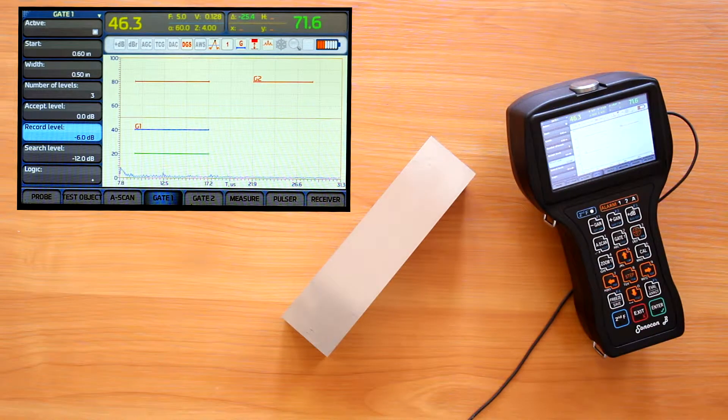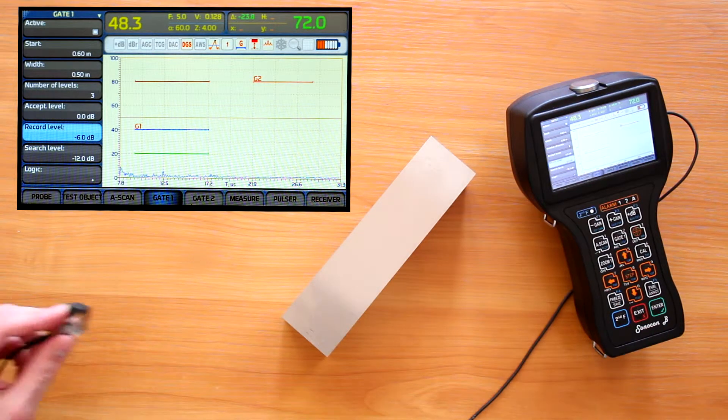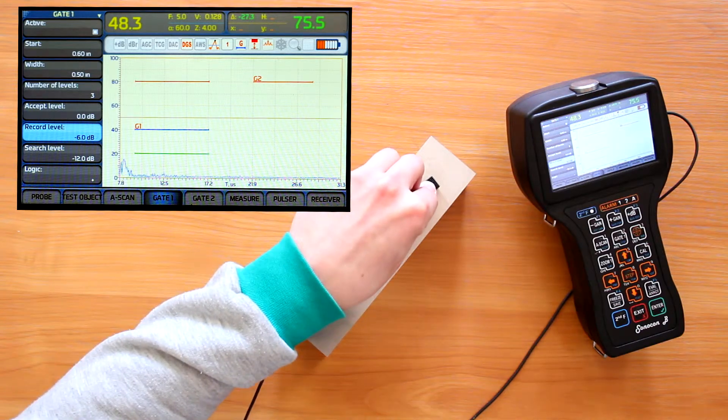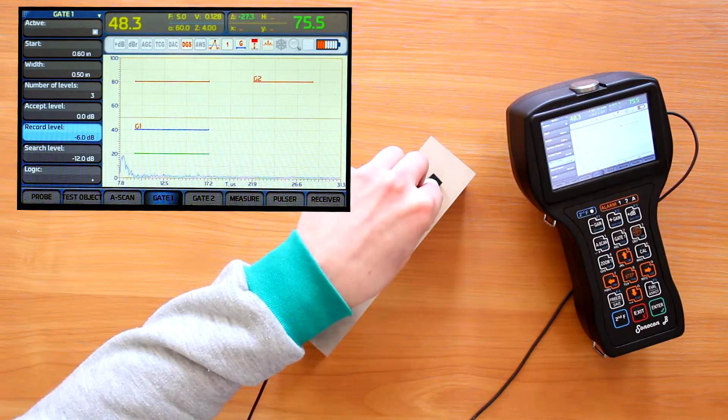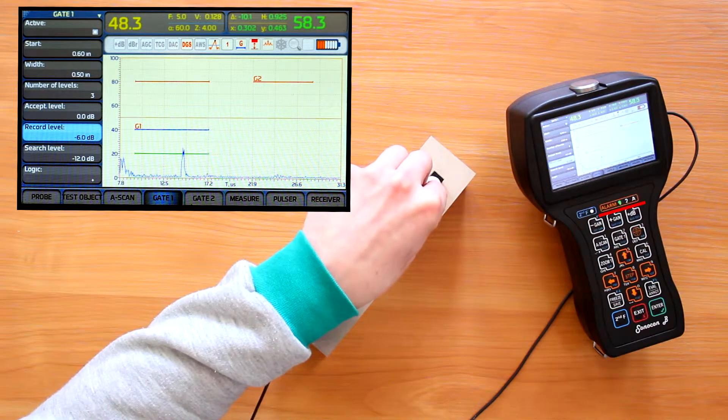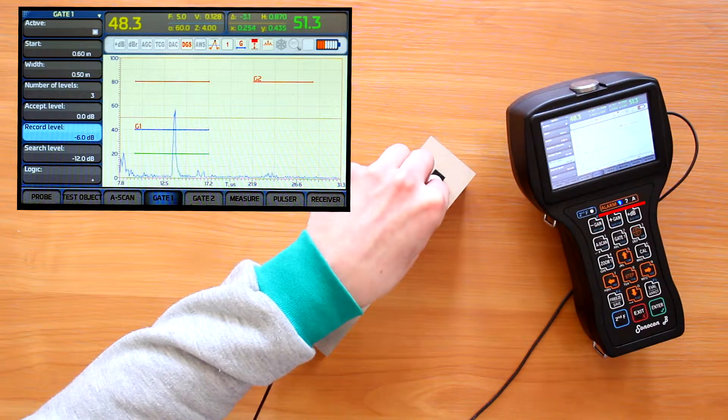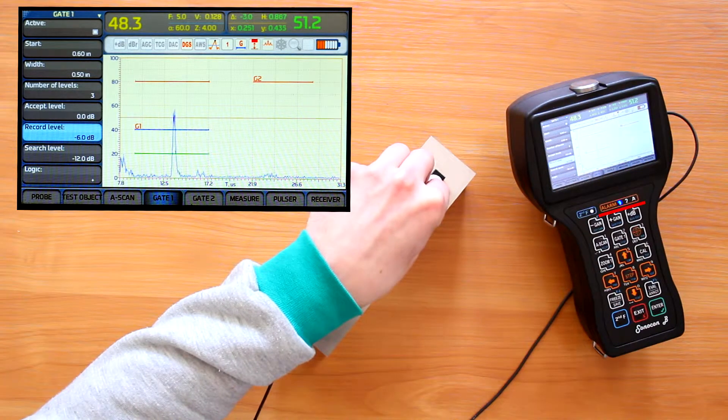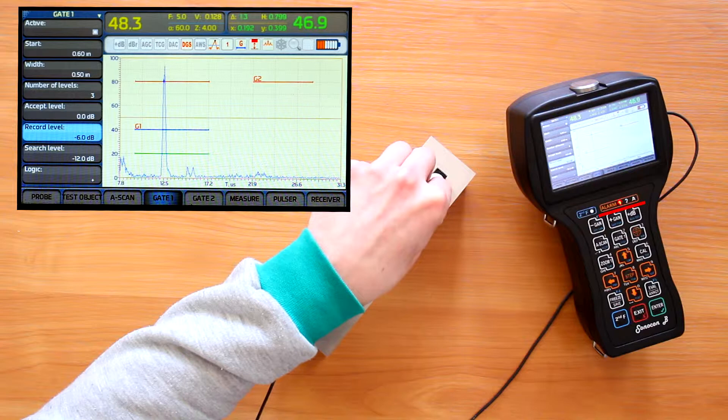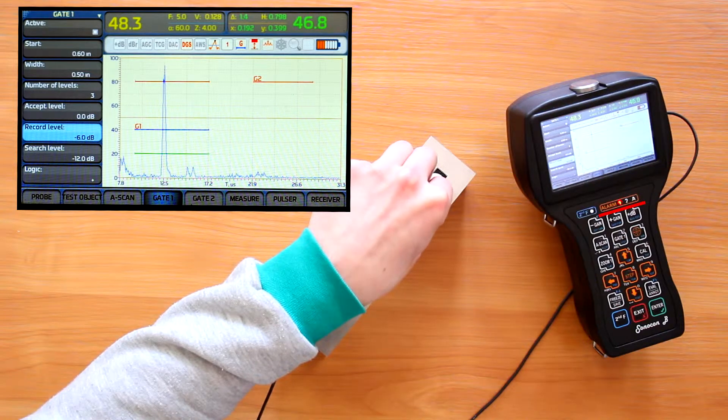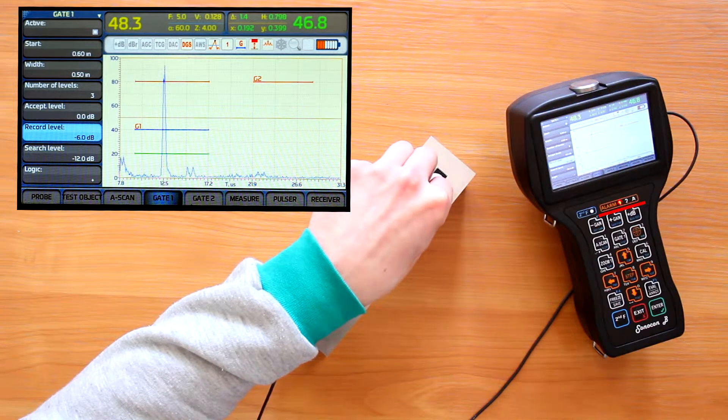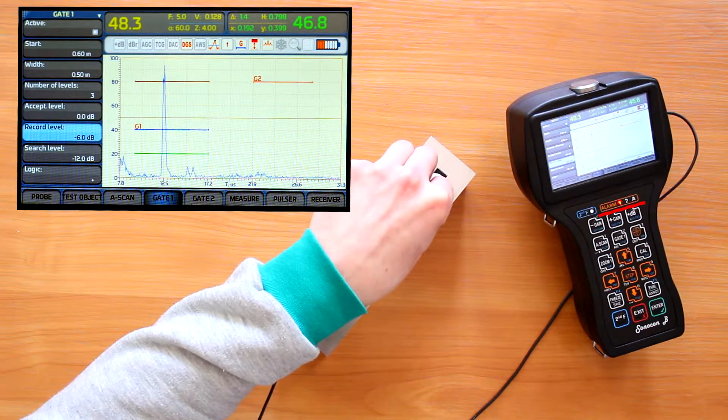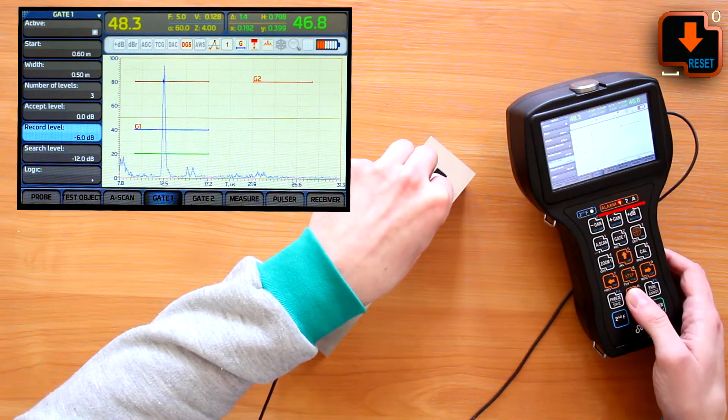In this case, we can forget about the gain change just observing alarm lights. It's turned green. We found something. Blue. We are to record the indication. Red. The acceptance level exceeded. This saves us time and attention. Let's concentrate on scanning.